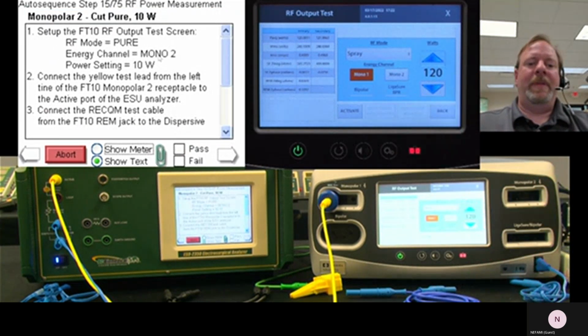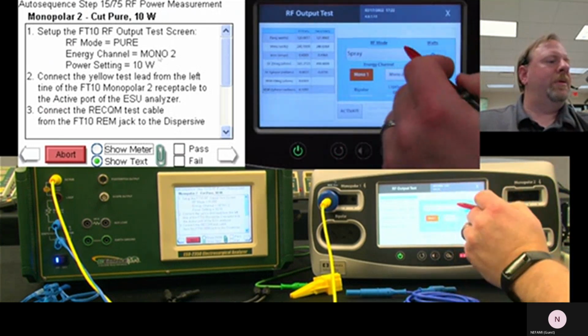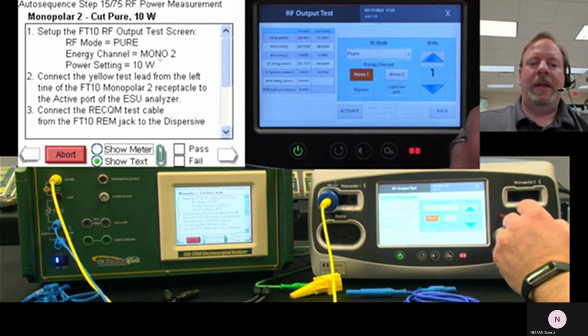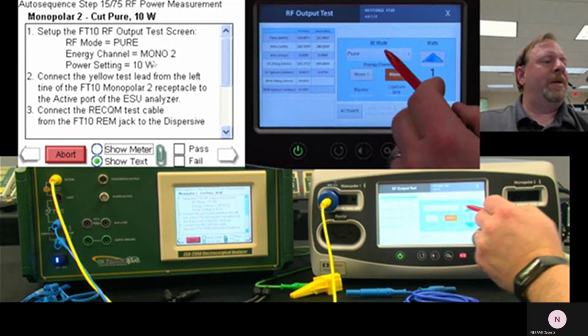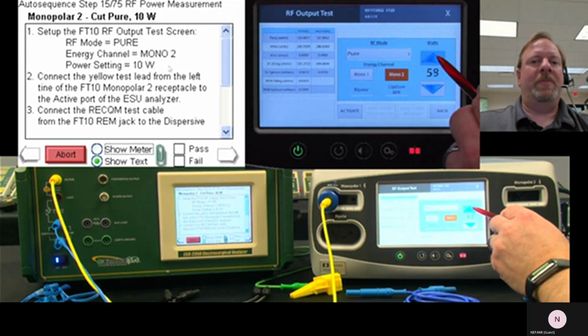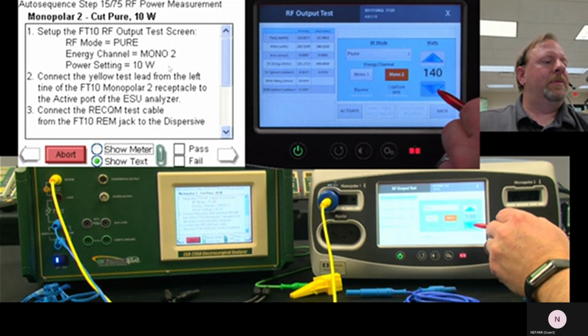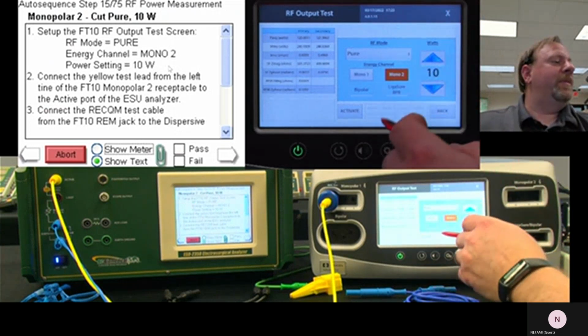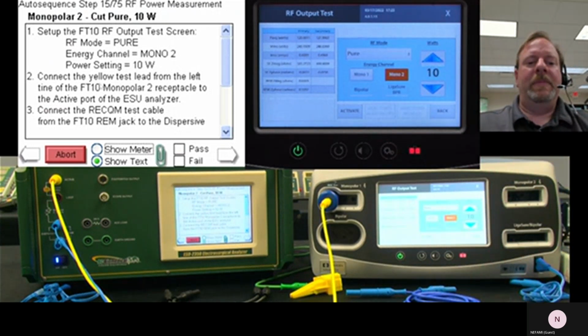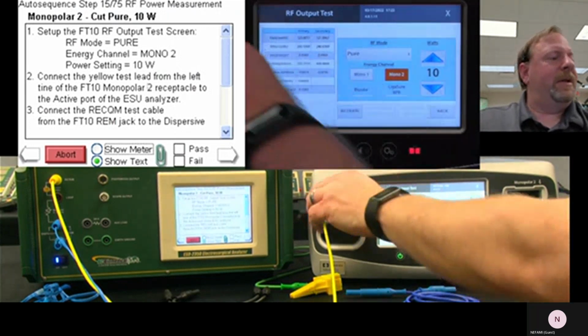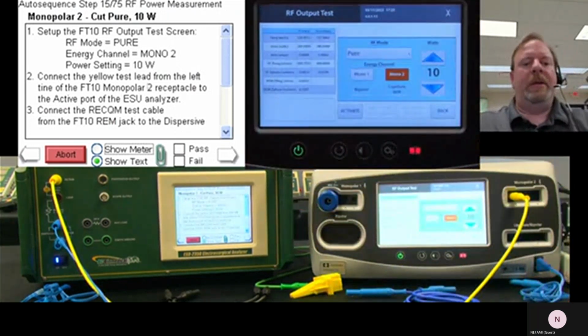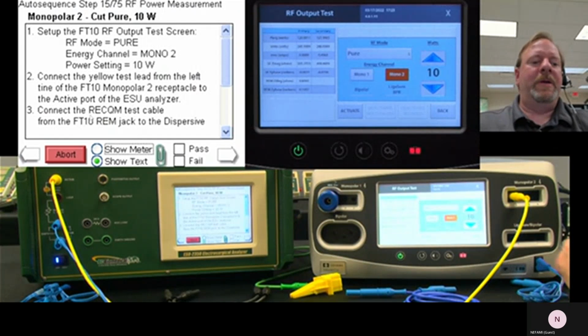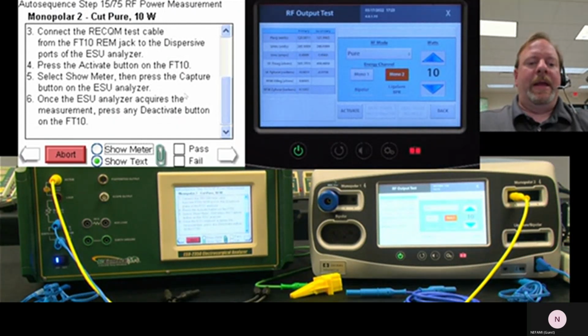Now we go on to the next step, and it says pure. So we're going to go in here, pure, and it tells me a power. We want monopolar 2. It tells me 10 watts. So we don't want to go too far like that. That would be bad. What happens when you're not paying attention. That's how you can fail a test, is by running the power way too high. So connect the yellow from the left tine of monopolar 2. And the REM is still connected, so we're good there. And then activate the generator.